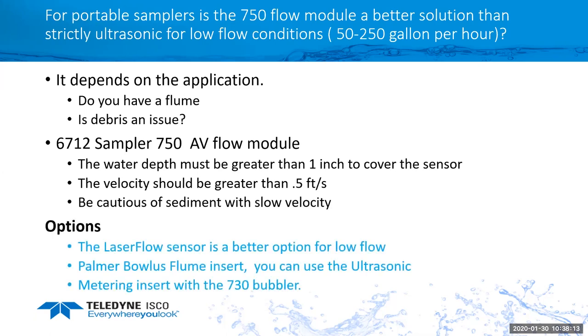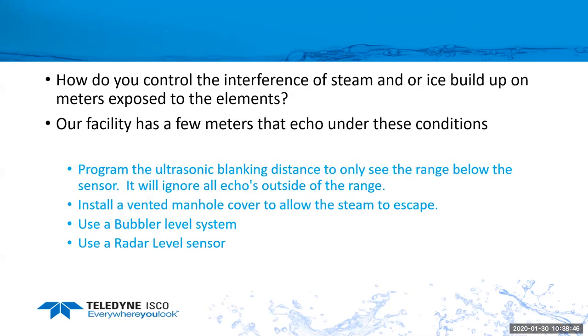So other options for that, especially if you have the slow velocity, is to use a laser flow sensor. It's going to be non-contact. We don't have to worry about debris collecting on it. Other options, depending on the channel, is to put a Palmer Bowlus insert in. Then you can continue to use your ultrasonic sensor, or consider using a 730 bubbler. I need a little more information on this application to better answer that. But the nice thing about the bubbler, if you did have issues with steam or foam, is that the bubbler would not be affected by those.